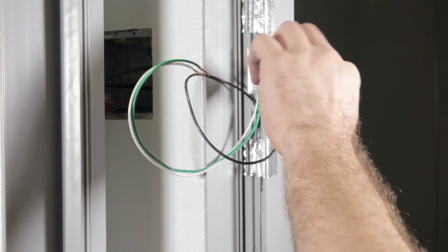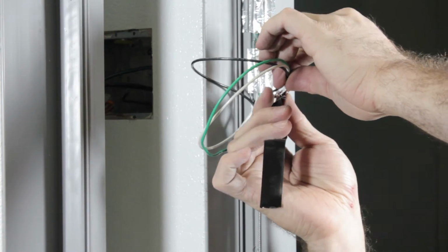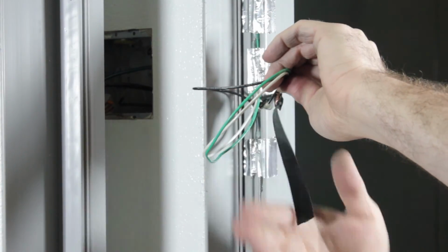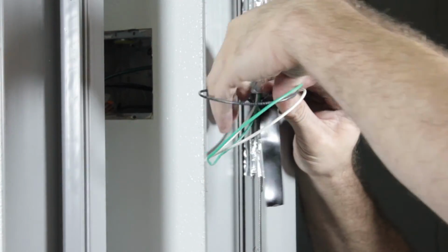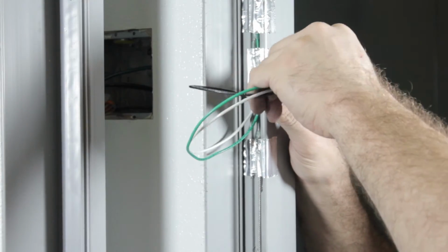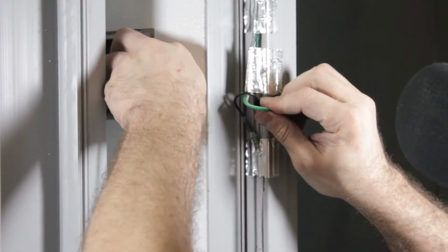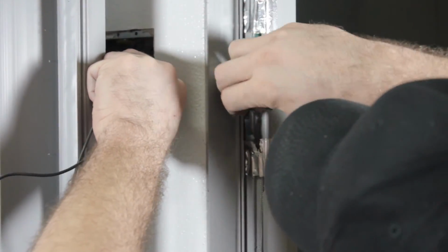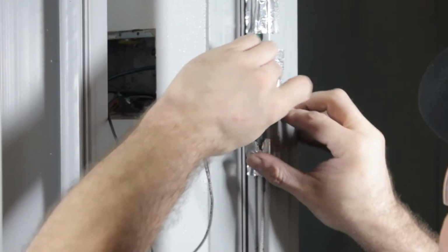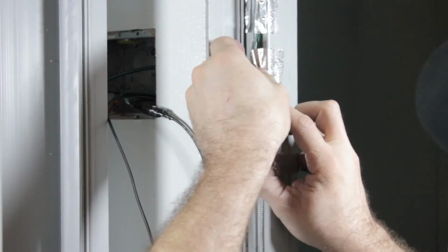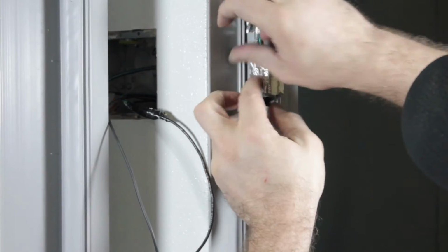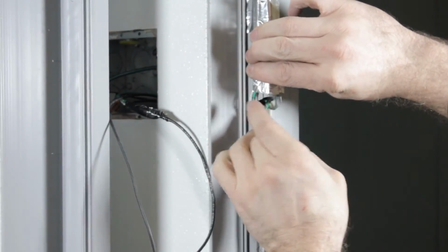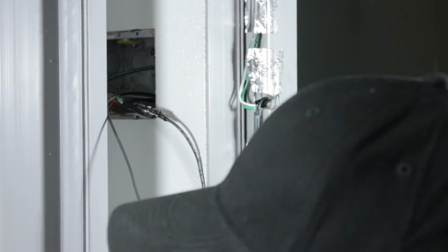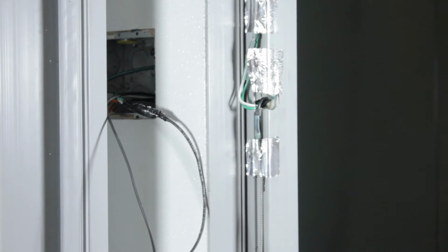Here's tip number 2. Once the heater cable is in place, then grasp one of the old wires and tape it securely to the new electrical leads. Use the old wire to pull the new leads through the frame and into the junction box. Carefully adjust the leads in the frame to avoid kinks that may damage the wires, and then check for electrical continuity before proceeding with replacement of all the panels.